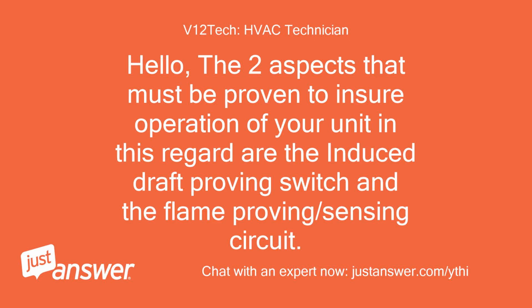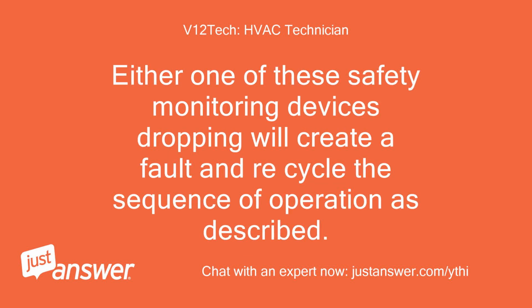Hello. The two aspects that must be proven to ensure operation of your unit in this regard are the induced draft proving switch and the flame proving/sensing circuit. Either one of these safety monitoring devices dropping will create a fault and recycle the sequence of operation as described.